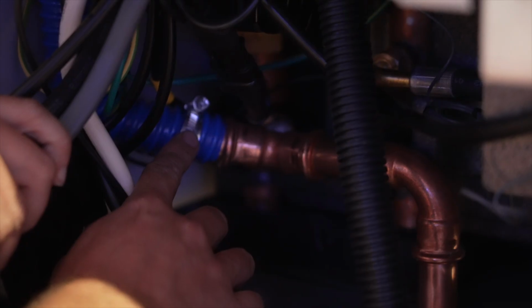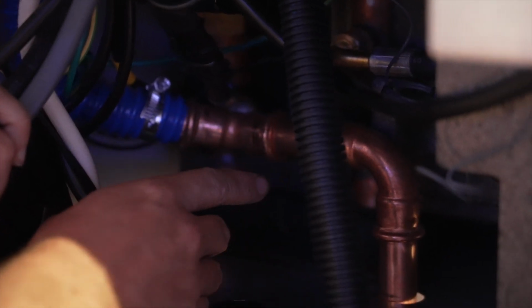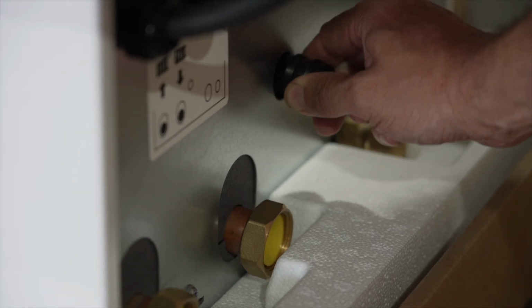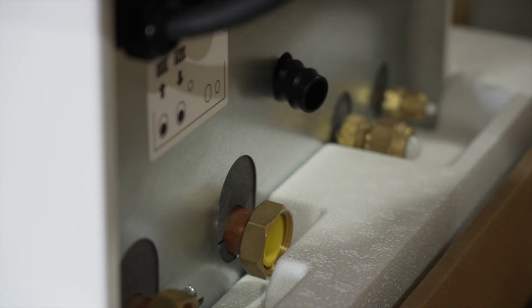For the PRV, you will find a flexible hose that goes to the bottom of the unit. There are a few solutions to getting this discharge to a drain or outside. Some installers like to use a 28 to 22 millimeter reducer under the unit. From the factory, you'll get a little plastic elbow that comes out of the discharge hole. Alternatively, you can connect pipework straight to the discharge hose using a Jubilee clip.